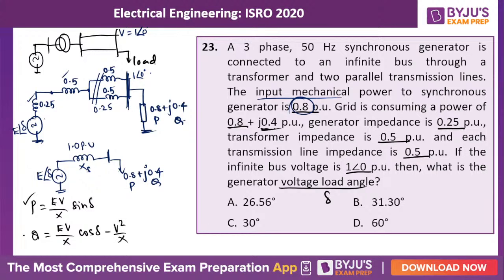I know the active power consumption by the load, I know the reactive power consumption by the load. If the load is consuming this much active and reactive power, who has to deliver? Obviously the generator has to deliver the same 0.8 per unit of active power and 0.4 per unit of reactive power. So substitute the values and you will get some equations. Substituting the active power value, 0.8 is equal to E, which we do not know, V, which I know is 1, and X. Altogether it will be the transformer reactance, line reactance and generator reactance, which is 1 per unit.